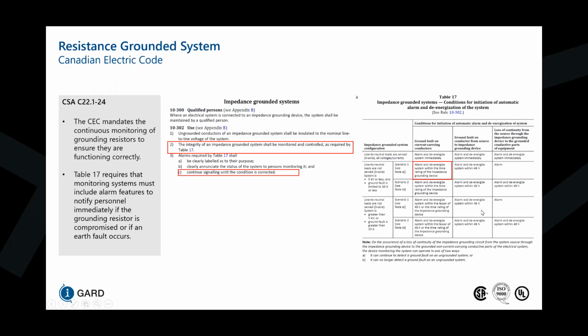When it comes to the short circuit and open circuit cases, for short circuit, it says to alarm and de-energize the system within 48 hours. So this is where we implemented a delay in our relays to allow for 48 hours to be implemented as a delay. And we also give you a pre-warning that the timer has started so that you're aware that this fault is in the system and you have up to 48 hours to clear it. When it comes to the open circuit condition, we either alarm if we can still detect a ground fault in an ungrounded system, and if we can't detect a ground fault in an ungrounded system, we alarm and de-energize the system within 48 hours. And this is true for both of the rows.